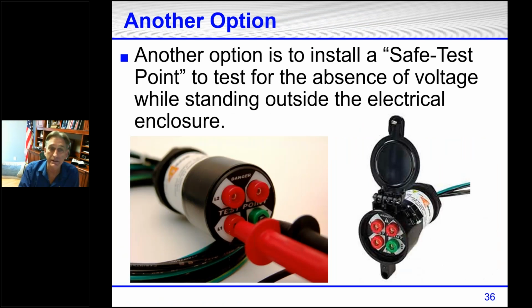But Grace has another option, and this is wonderful. I think this is better than sliced bread. Another option is to install a safe test point to test for the absence of voltage while standing outside the electrical equipment, before you even open the equipment up. You've turned off the power, you've gone through the steps, you get to step number 7, and you're testing for the absence of voltage. You test your tester, then standing outside the equipment, you test phase to phase and phase to ground of all the circuit parts. Then you test your tester again, and at that point you have established and verified the equipment is in an electrically safe work condition. You can open the equipment up without wearing shock or arc-rated PPE.